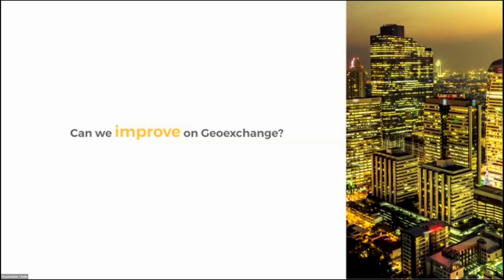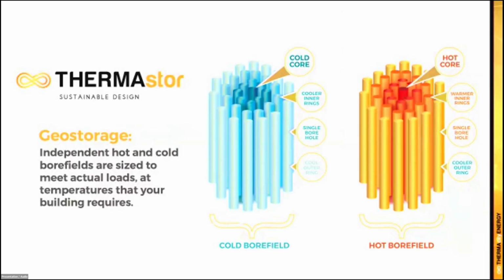So innovation number 2 is the introduction of what we're calling geostorage. This is not dissimilar from GeoExchange, it's the same holes in the ground, the same pipes in those holes, the same grout, the same drilling. There's very little technically different, but what we're doing is separating hot and cold thermal storage into separate bore fields. This provides 2 distinct benefits: first, we can intentionally mismatch the size of these bore fields to better meet the building's seasonal needs, so we no longer need to balance heating and cooling loads throughout the year.